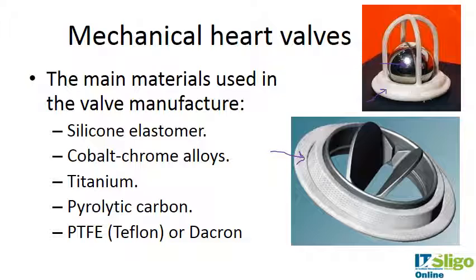In the bileaflet valve, the frame has a titanium structure covered in a woven mesh-like structure of polytetrafluoroethylene or Dacron, which is sewn into the patient's tissue and forms a tight bond. As the name Teflon suggests, this woven fabric is non-stick, minimizing blood clotting. The leaflets themselves are graphite coated with pyrolytic carbon. Pyrolytic carbon, as discussed earlier in the course, has very low thrombogenic capability, so there is very little opportunity for blood clotting.